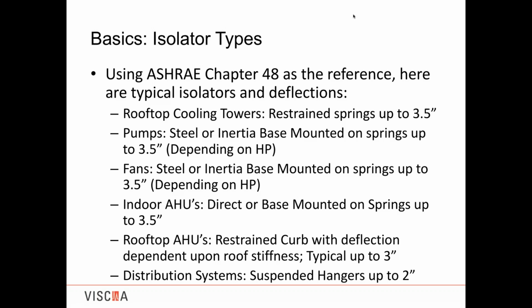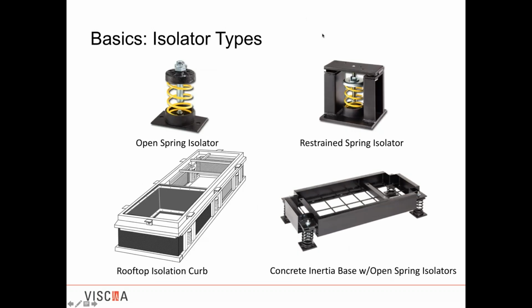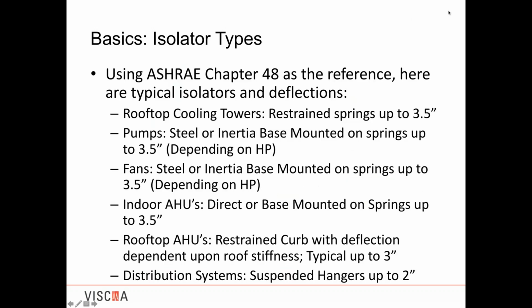Now, if you see on this chart, let me go, I went back one too far. If you see on this chart, all the deflections will say up to a certain number of inches. So cooling towers, spring up to 3.5 inches. The "up to" is very important since, one, it is somewhat related to the RPMs, but like I was saying with the diaphragms, it's also related to the stiffness of the support structure underneath.